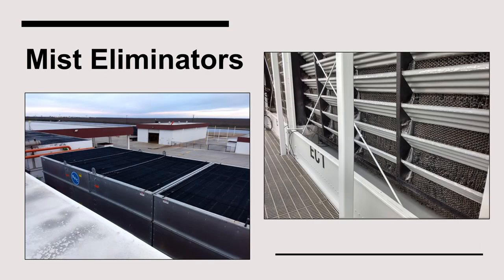Mist eliminators are installed on evaporative condensers for the purpose of limiting the amount of water that splashes out of the condenser. Mist eliminators are installed on the top of forced draft evaporative condensers and on the side of the unit for induced draft condensers. Mist eliminators should be regularly cleaned to prevent excessive scale or algae buildup. These will also need to be replaced if they begin deteriorating from sun exposure.